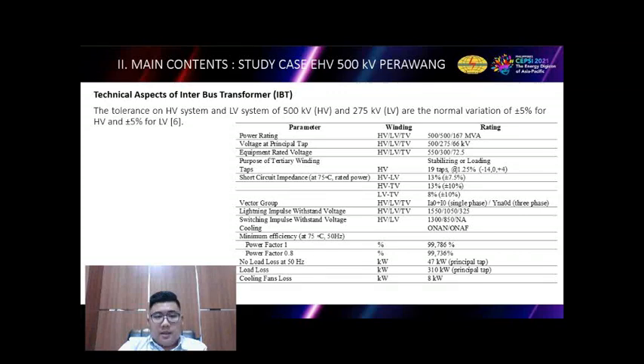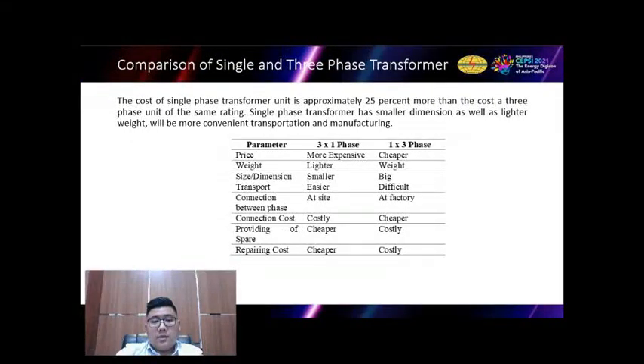Now we continue to the main content, the case study of EHV 500 kV Perawang. This slide is all about the technical aspect of the interbus transformer, IBT. The tolerance on the HV system and the LV system of 500 kV and 275 kV are the normal variation of 5% for HV and 5% for the LV. The parameters in the interbus transformer consist of power rating, voltage at principal tap, equipment rated voltage, purpose of tertiary winding taps, short circuit impedance, vector group, lightning impulse withstand voltage, switching impulse withstand voltage, cooling, minimum efficiency, no load losses, and cooling fan loss. Now, we continue to the next slide.